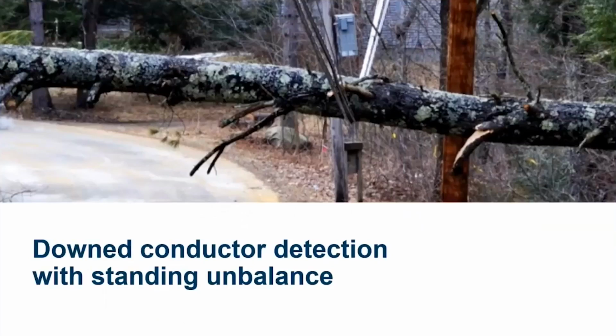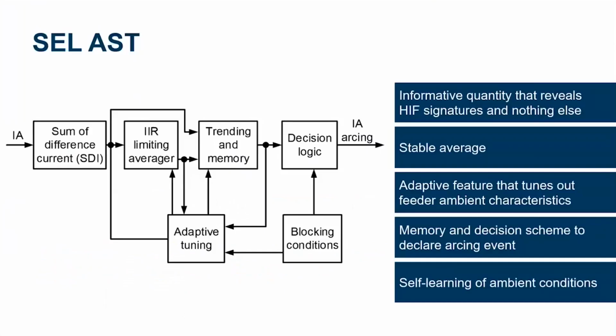As mentioned before, we need a dedicated element to detect high impedance faults. And that is where SEL ArcSense technology comes in. AST is designed to specifically detect the arcing that is associated with a high impedance fault. In most cases, when you have a high impedance fault, you're going to have intermittent arcing in that fault, and that arcing is very rich in harmonic content. So we're going to look at the harmonic content of the measured current and use that information to detect high impedance faults in the system.